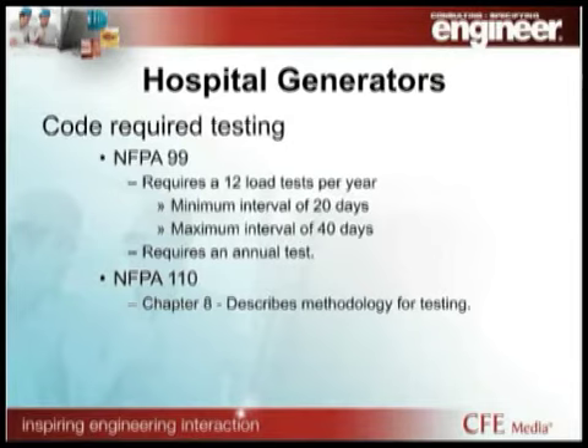So with all of that said, I'm going to talk a little bit about code-required testing, and we'll come back to the statement about calculating loads. Hospital generators are required to be tested, and they're required to be tested monthly, and they have some intervals in there, and they also have criteria for how to test them in NFPA 110. There is a requirement for an annual test, but that's only if your minimum load on the generator is less than 25%. Some facilities follow that guideline just as an added protection and confidence builder, but it's certainly not required if you've designed your system and sized it accordingly. That goes back to sizing your generator down to your loads.